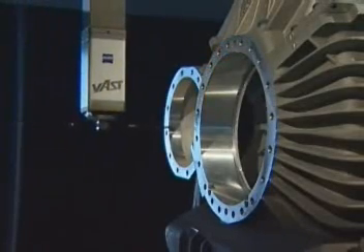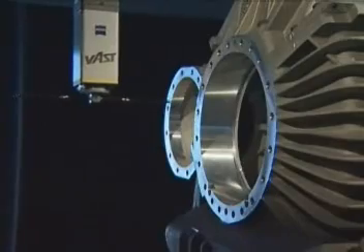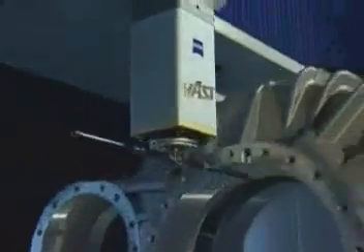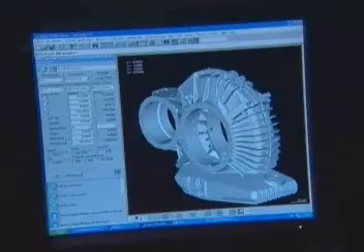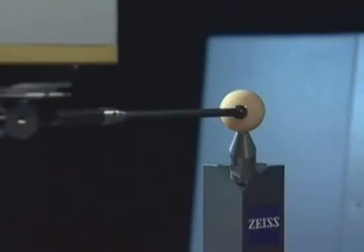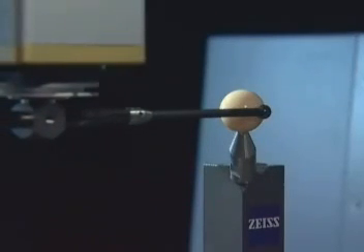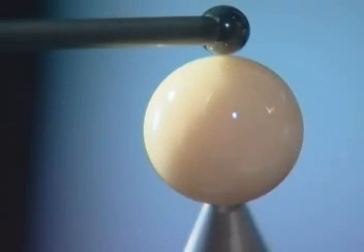VAST Navigator is now the third generation of scanning from Carl Zeiss. The advantages in detail: increasing productivity is our goal. Dynamic calibration, with two speeds exclusively on the calibrating sphere, compensates for stylus bending.